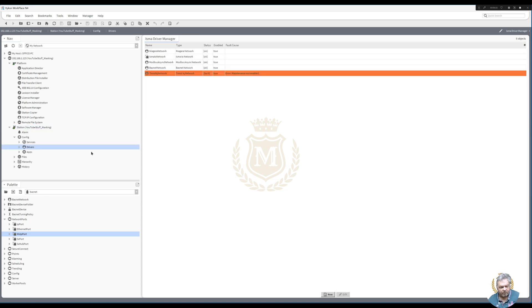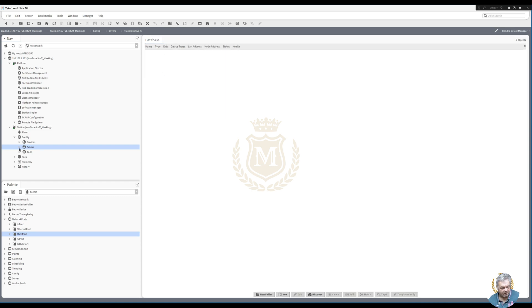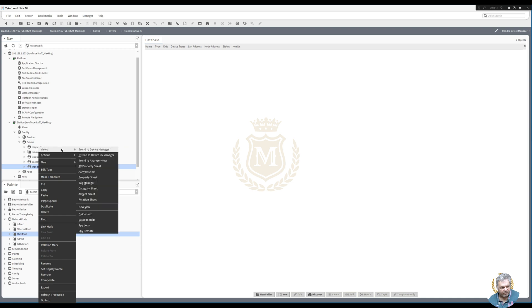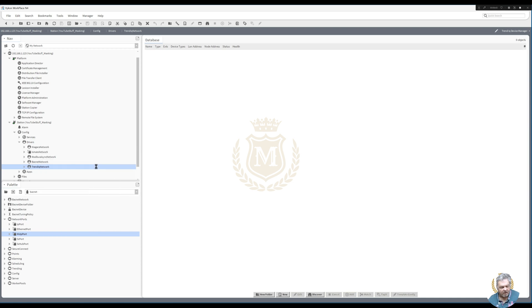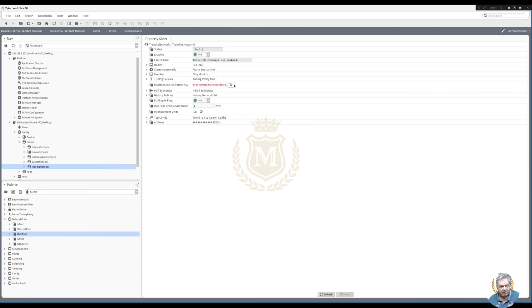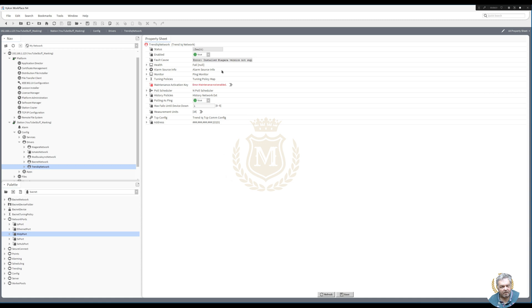Let's go to Config > Drivers. There's an error: 'Maintenance not enabled.' So let's right-click that, go to AX Property Sheet, and we've got to put a maintenance key in here and save it.